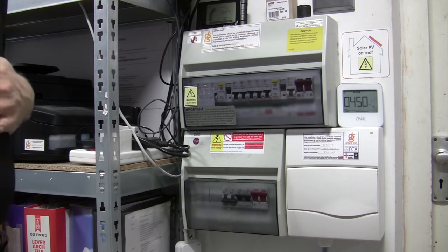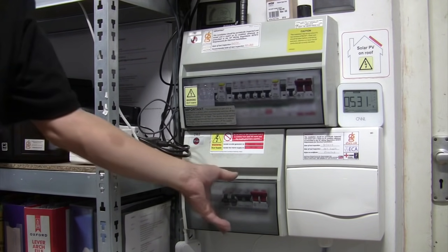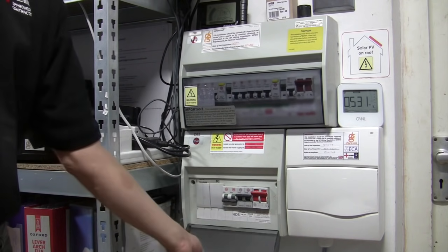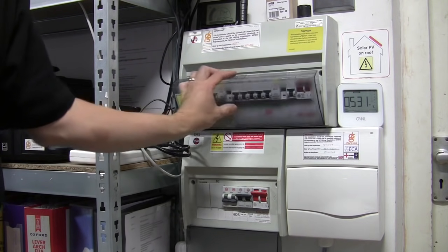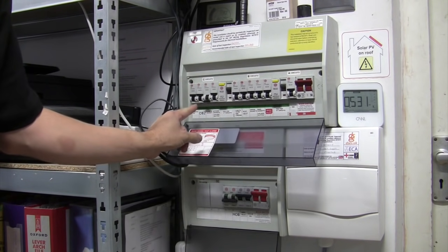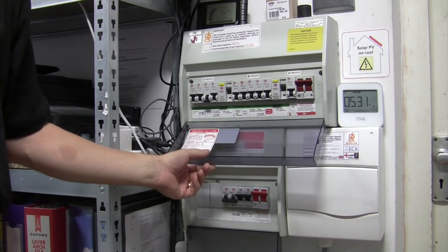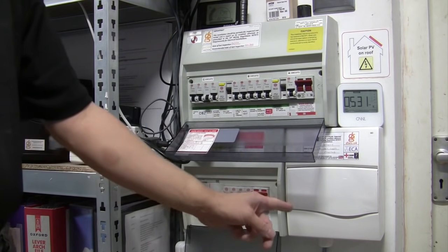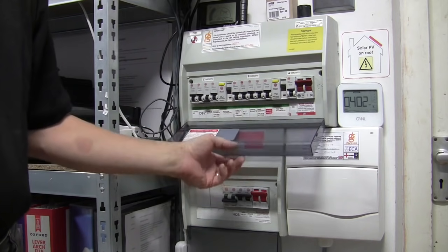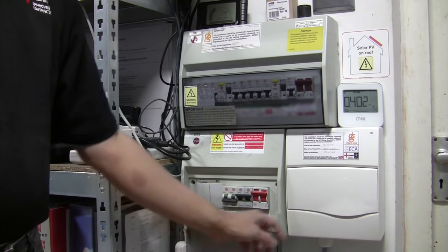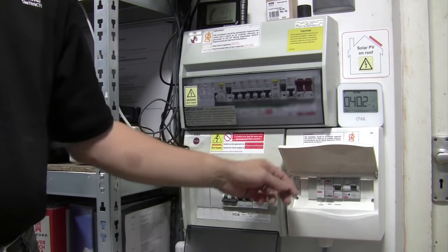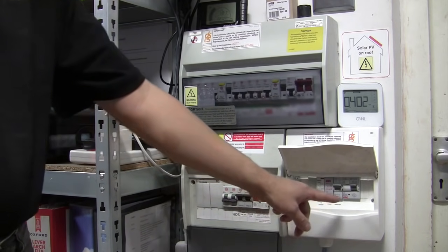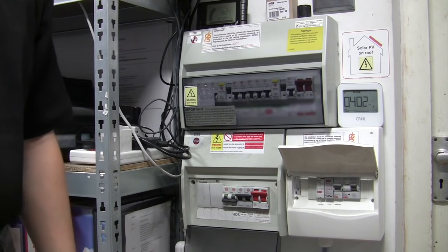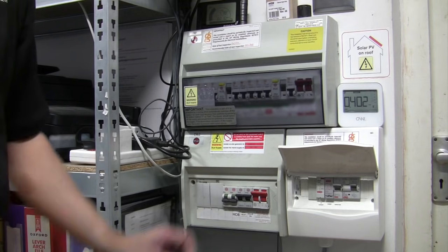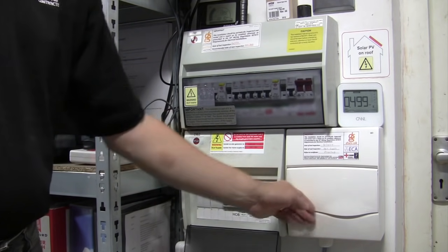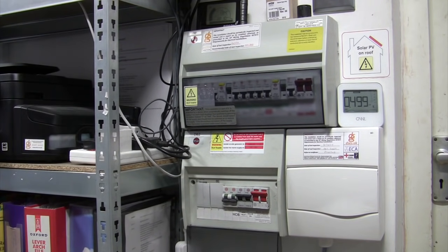metre. I'm installing this device into DB2 on my installation, which is an Elex board that's hanging off an RCD protected way from DB1, which itself is a dual RCD high integrity board. DB3 is on the high integrity or non-RCD fuse way from DB1, and that's because DB3 is for my electric vehicle charge point, which itself requires connection via a Type A RCD rather than a Type AC, to prevent nuisance tripping from any DC components introduced onto the AC waveform.